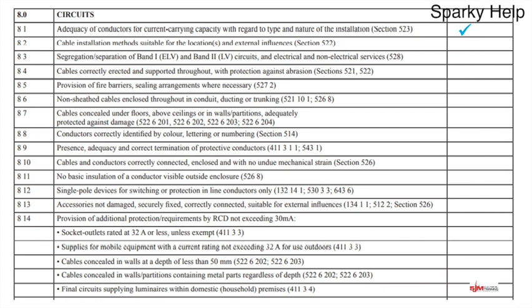Cable installation methods suitable for location and external influences. If we've got twin and earth clipped direct to the wall and it's within a machine workshop, it might pass electrically and test okay, but is it the most suitable cable for that environment? Probably not, and therefore you might recommend it gets changed or not pass it depending on your point of view. It might be damaged already, so it's about whether whatever's been installed is suitable for that location.